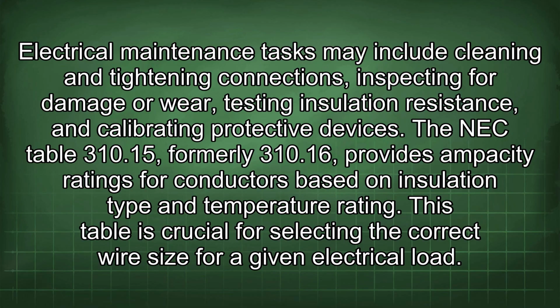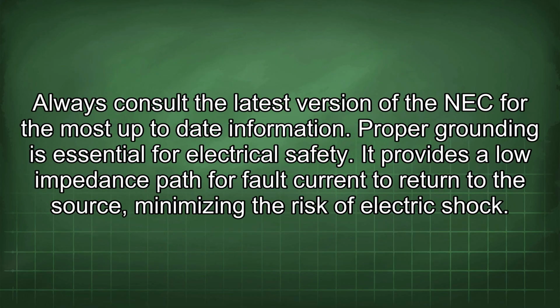The NEC Table 310.15, formerly 310.16, provides ampacity ratings for conductors based on insulation type and temperature rating. This table is crucial for selecting the correct wire size for a given electrical load. Always consult the latest version of the NEC for the most up-to-date information.